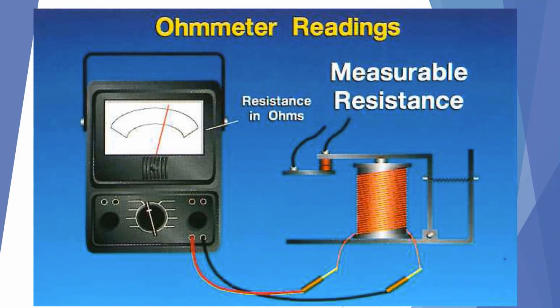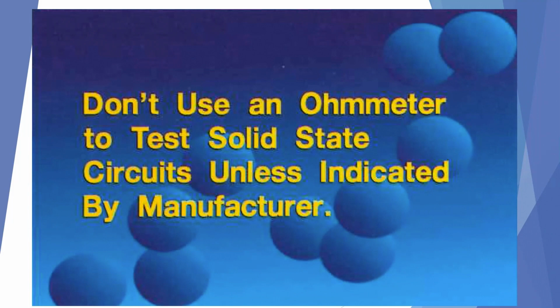In this example, we are measuring a measurable resistance across the coil, which would be normal. Sometimes the resistance value is given to you on certain devices, and if it's within the range as designed, that's good. If you're exceeding that range, it could be because the wires are breaking down in that coil and the device is failing. In most troubleshooting guides, you will see this warning to not use an ohm meter to test solid-state circuits unless indicated by the manufacturer.